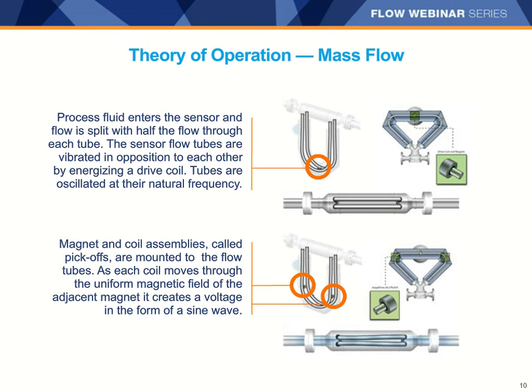When there is flow in the Coriolis meter, the effect on the tubes twists them like you see here on the bottom. Magnet and coil assemblies called pickoffs are mounted to the flow tubes as seen in the center bottom cutaway. Each coil moves through the magnetic field of the adjacent magnet and creates a voltage in the form of a sine wave. Most implementations use a pair of counter-vibrating tubes to cancel the effect of external vibrations, but many geometries exist to meet various application requirements or to avoid patent infringement.